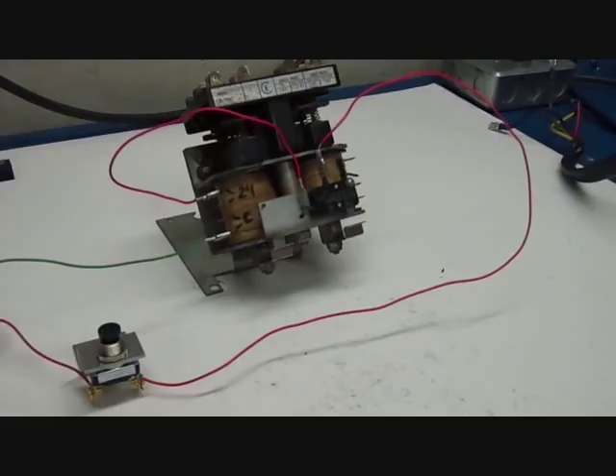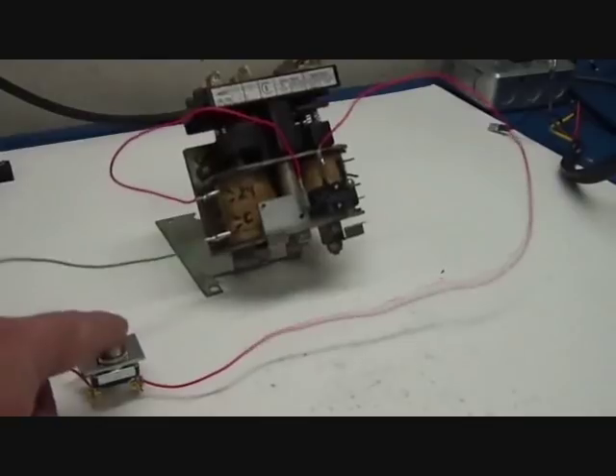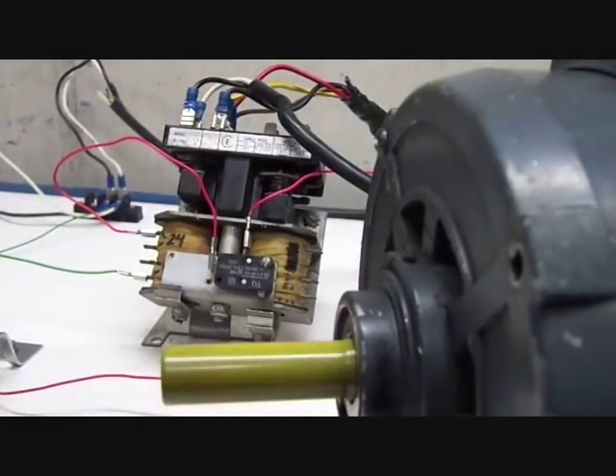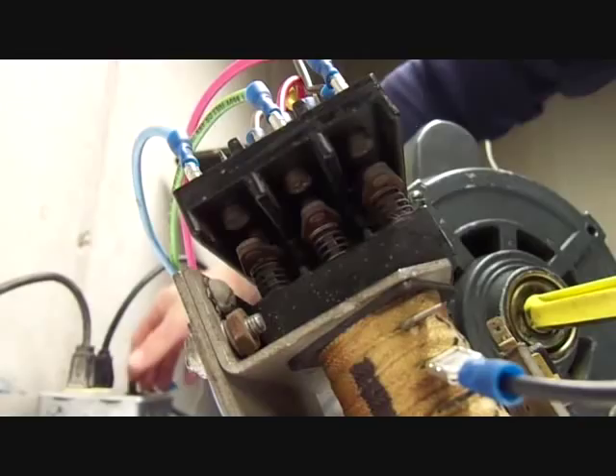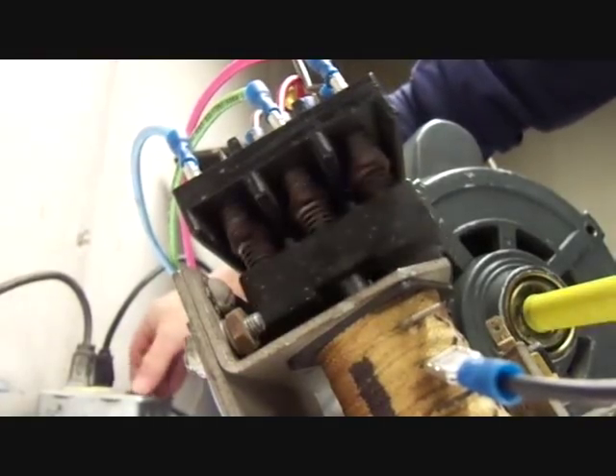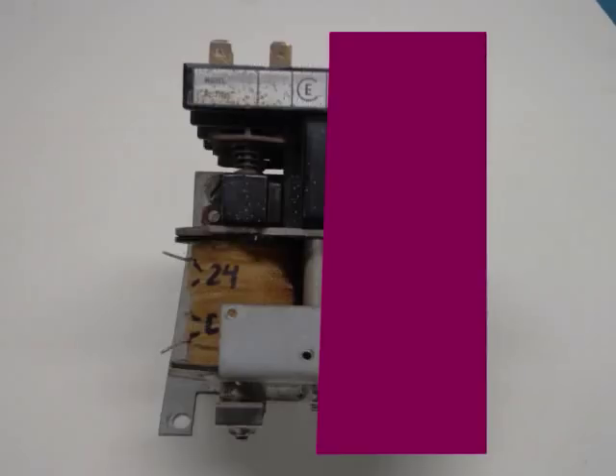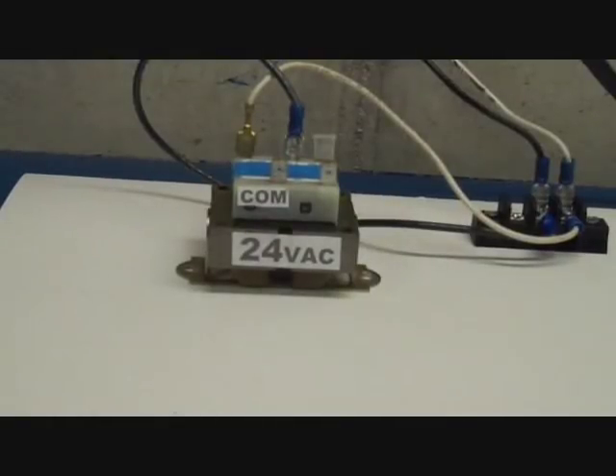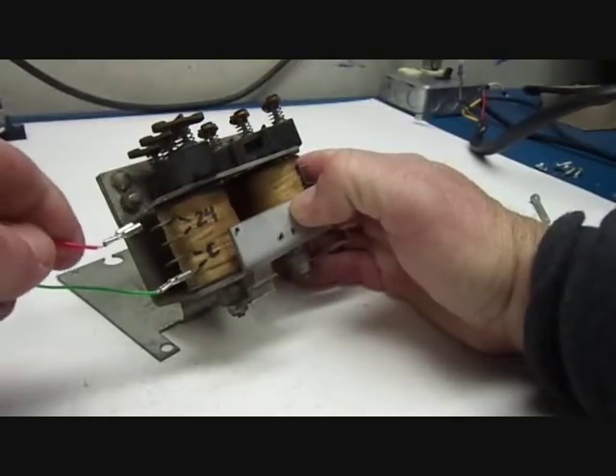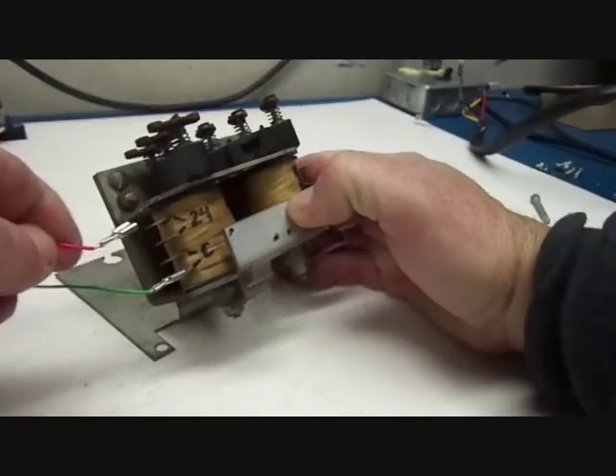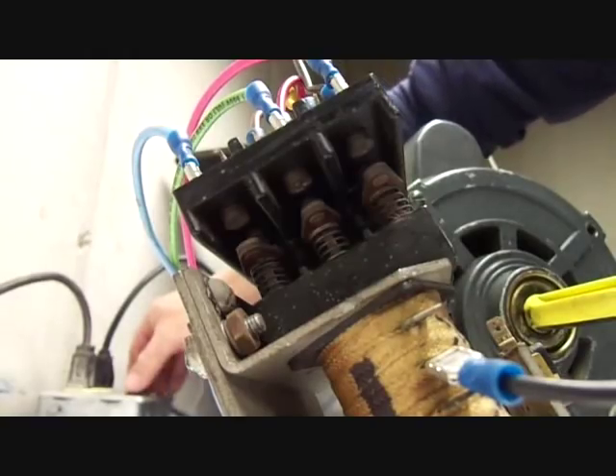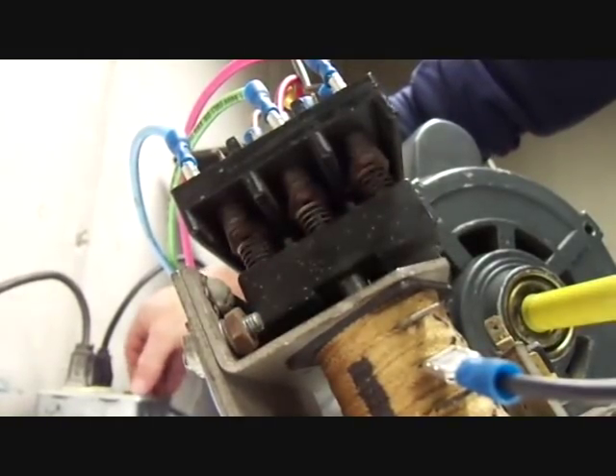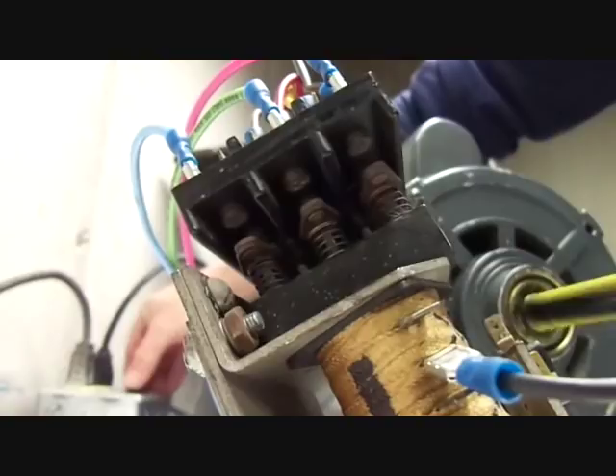This is an old-school reversing contactor, so it's basically two identical contactors interlocked together on a single frame. One side is to run the motor clockwise, and the other side is for counterclockwise. But forget about the one on the right for now. Let's just pretend we have a single contactor. It has a 24-volt AC coil, like most of them do, which pushes or pulls together the high-voltage contacts, allowing current to flow to the motor.